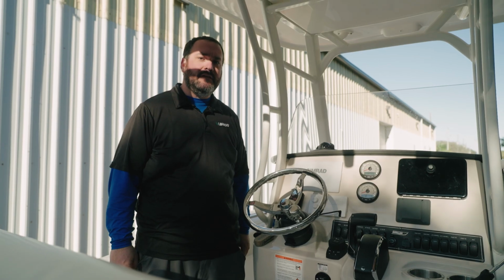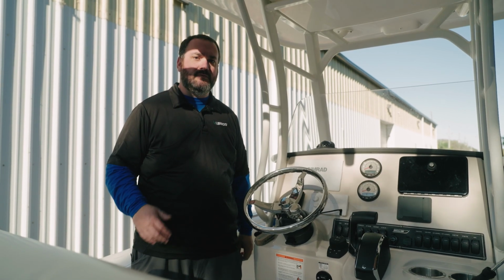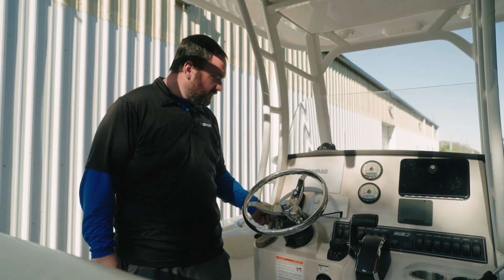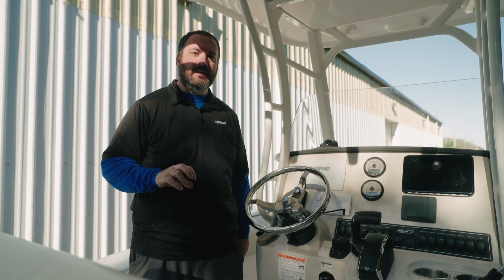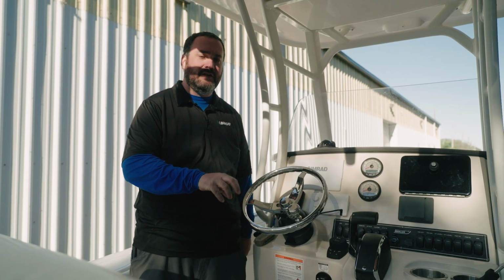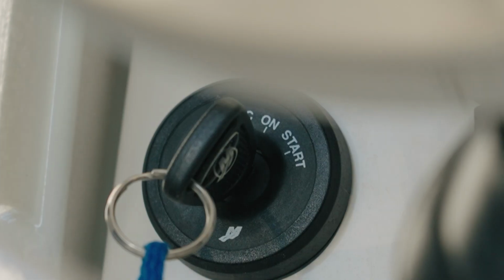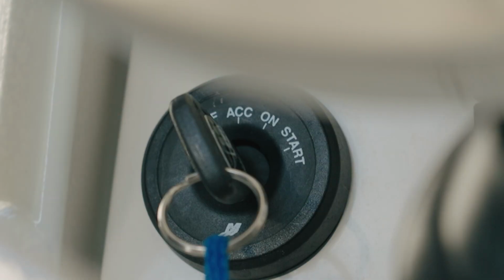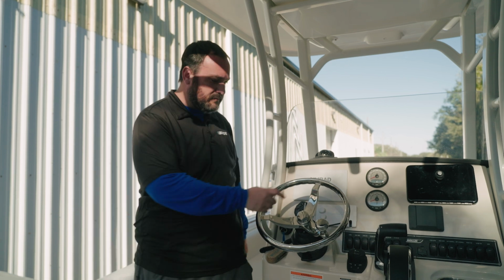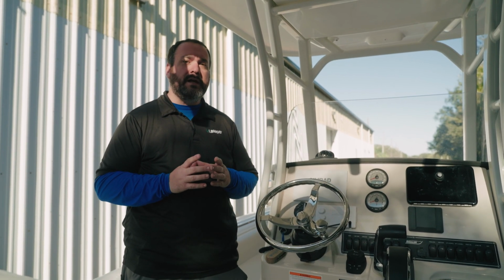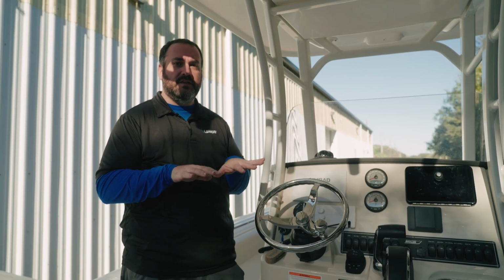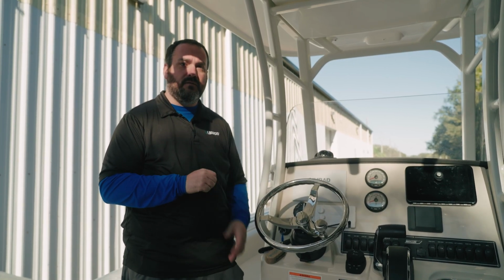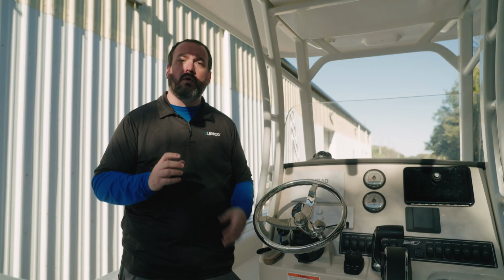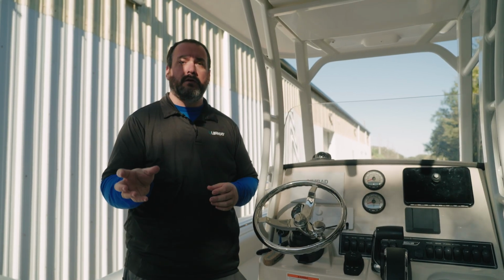And now that we've verified that the actuators are functioning and the system is ready, we're going to turn the key switch off at this point before turning the vessel power off through the battery switch to trigger a store in the system's memory of all these settings. Now that the key switch is turned off and the system is in standby mode with the vessel's battery still on, we want to wait at least 90 seconds for everything to save and store in the system before turning the key switch back on again or before turning the vessel power off.